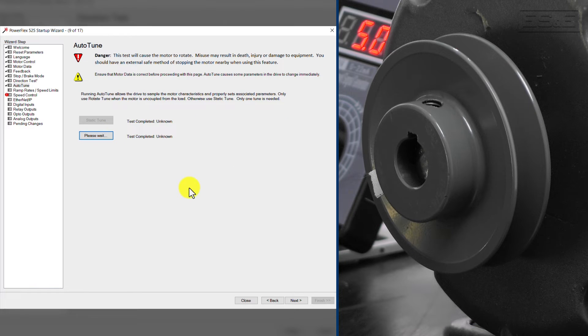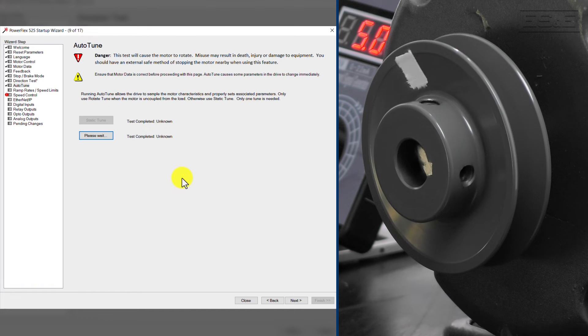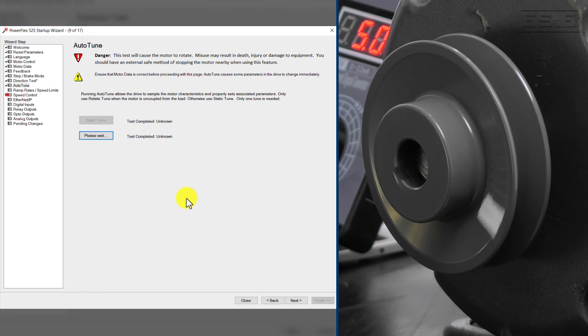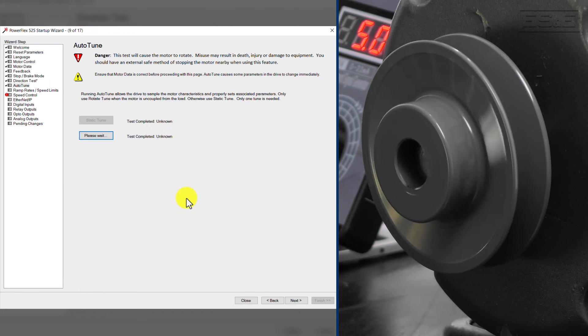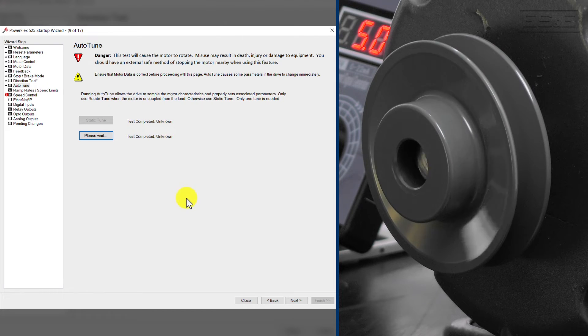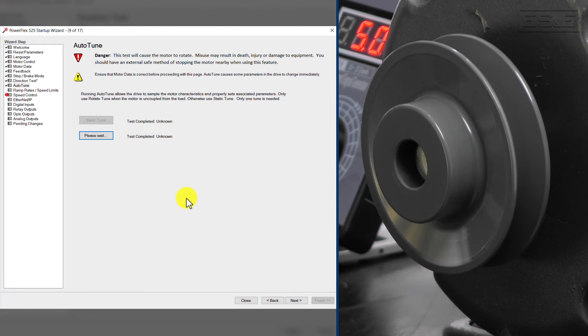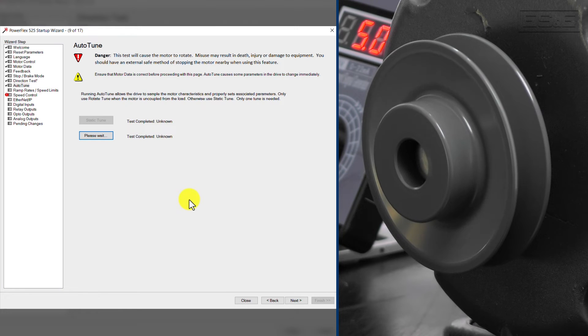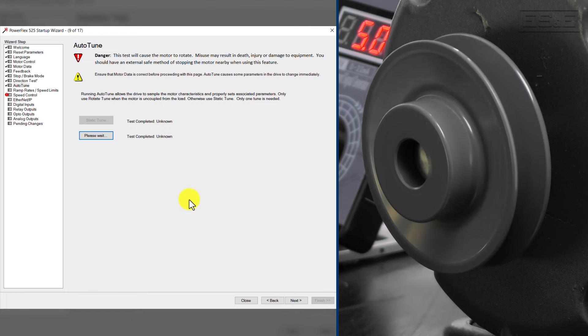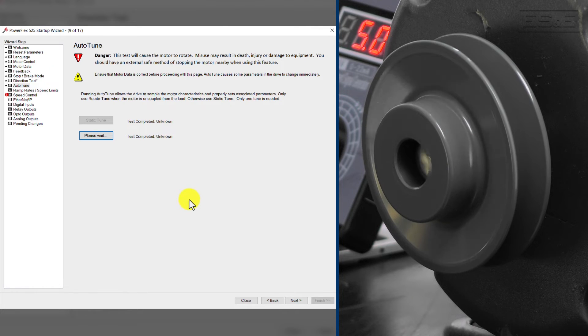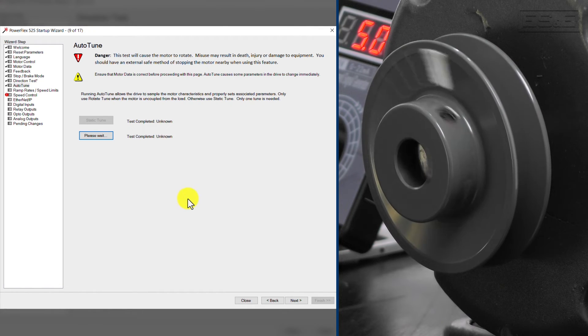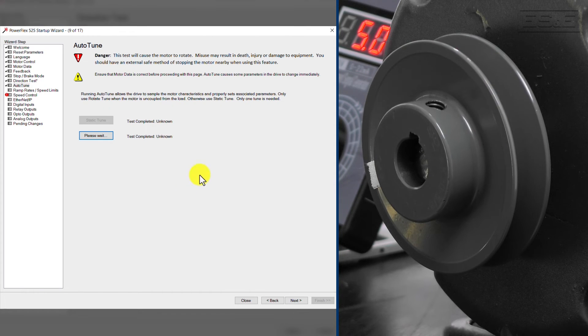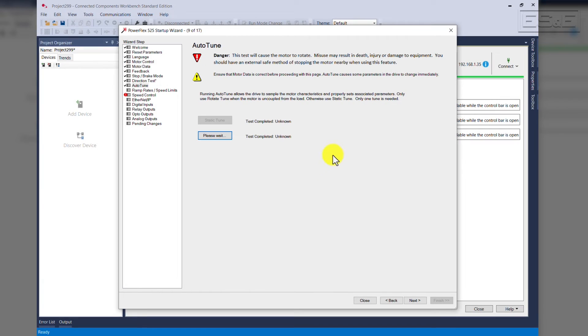The drive will start, and please observe the motor. It will start turning very slowly, and then speed up. As you can see, the motor went to 45 hertz, and then it will slow down and stop. Once the Rotate Tune is complete, you'll get the test completed, Yes, and click Next.